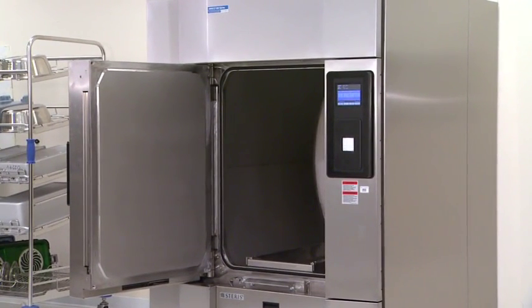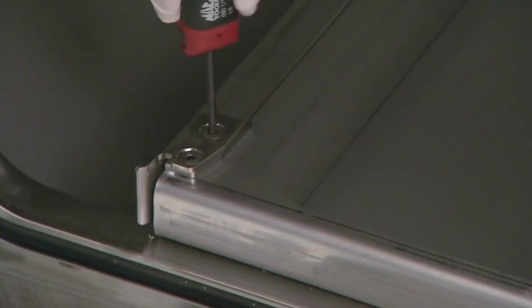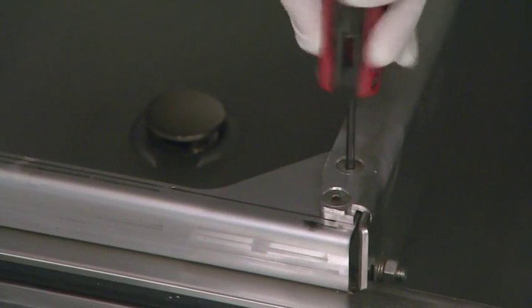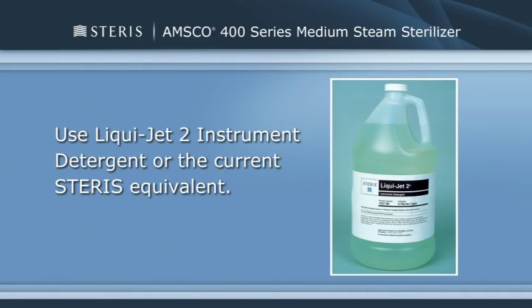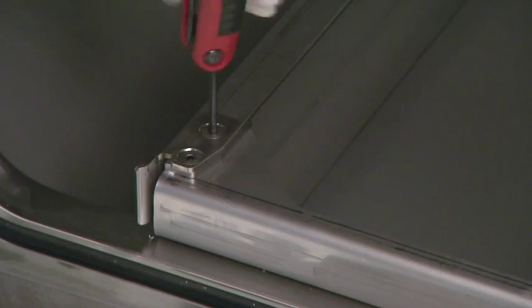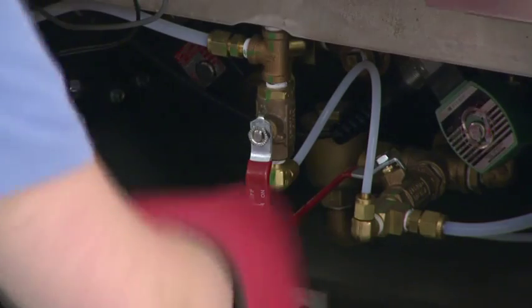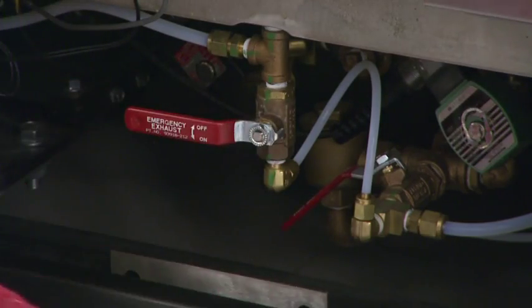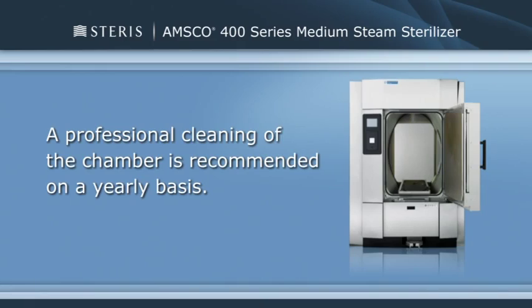Remove shelves from the rack. Use a 1/8-inch hex wrench to loosen but not remove the set screws at the front of the rack assembly. Remove the rack assembly from the chamber. Wash the inside of the chamber and the shelf assembly with a mild detergent solution such as Liqui-Jet 2 instrument detergent or the current STERIS equivalent. Once the chamber is clean, replace the shelf assembly. Close the emergency manual exhaust valve. A professional cleaning of the chamber is recommended on a yearly basis.